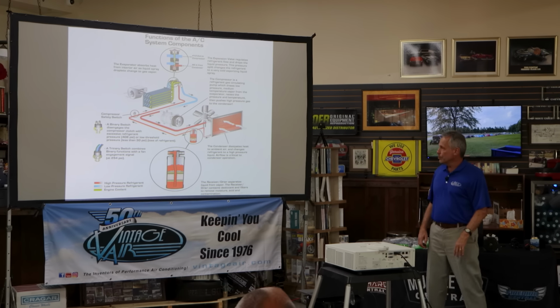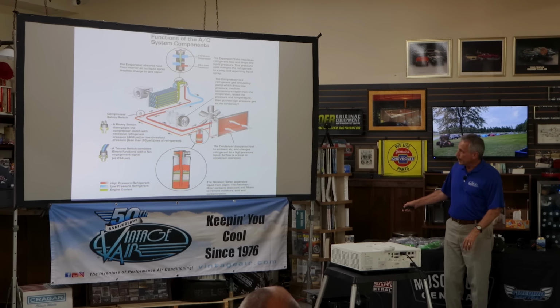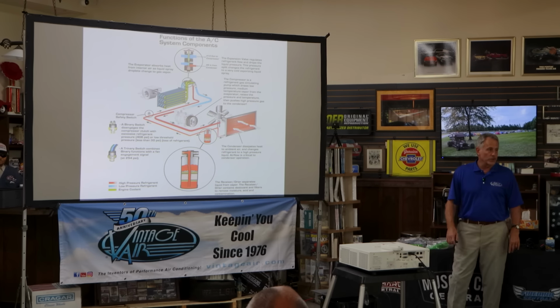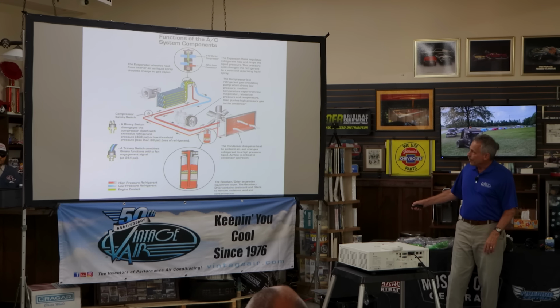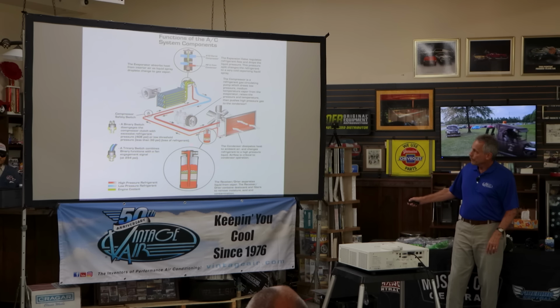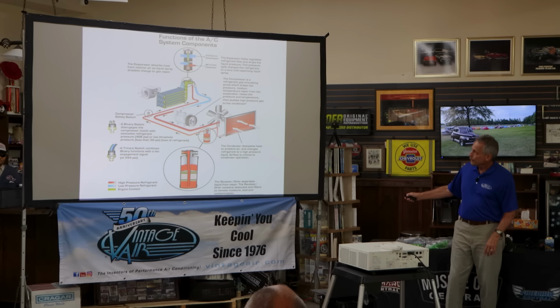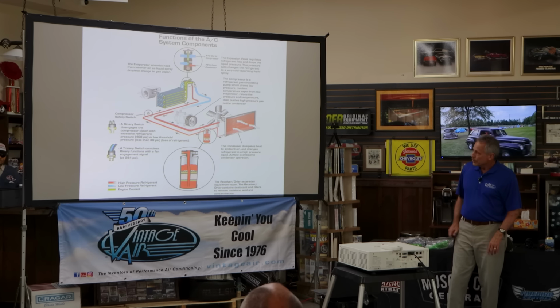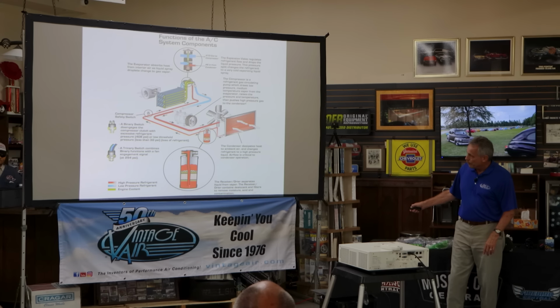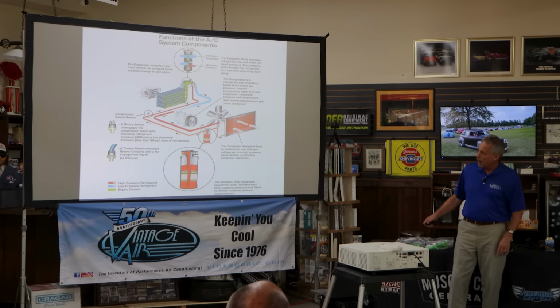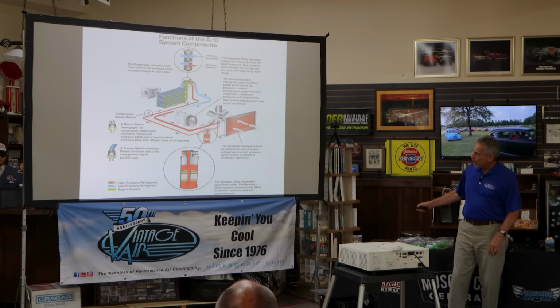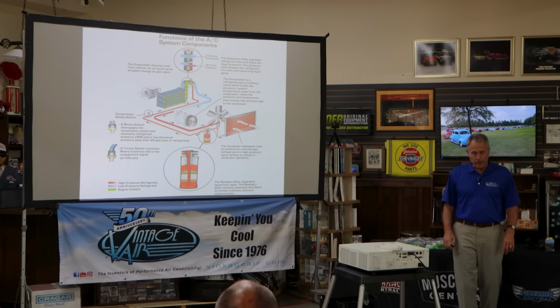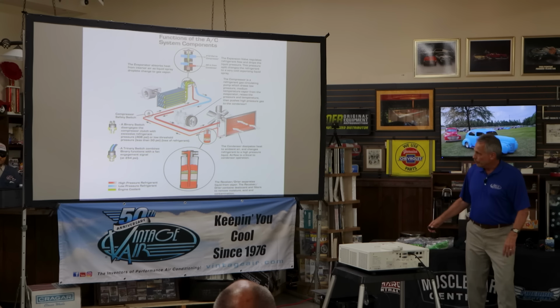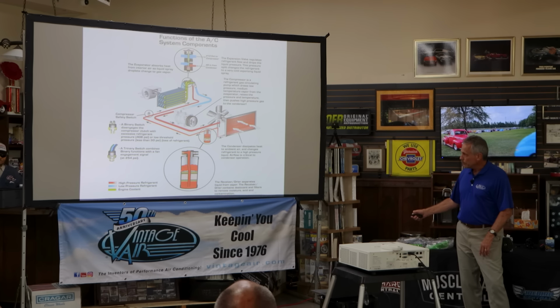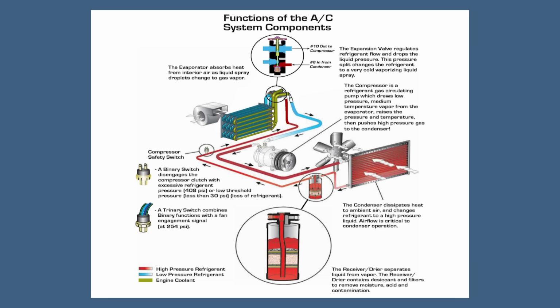The third thing the receiver dryer does is provide a liquid seal, so we get nothing but liquid refrigerant going to the next stage, heading to our expansion valve. The pickup tube is at the bottom of the receiver dryer, and when the system is charged properly, the level in the dryer is about halfway full.